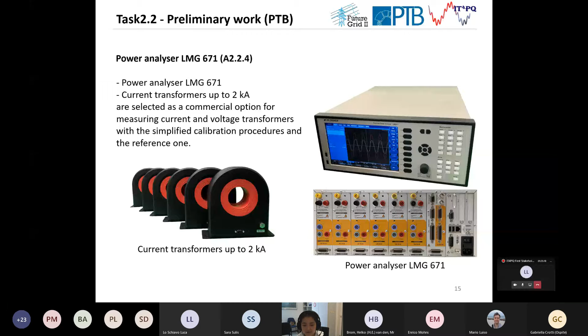3. All activities have not been studied yet, but one device is presented for this part, that is for a comparison of simplified procedure results with the references. PTB offers this power analyzer LMG671 with current transformers up to 2 kA as a commercial option for measuring current and voltage transformers with the simplified calibration procedures and the reference one.